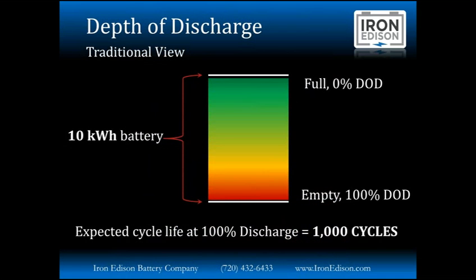Let's take a look, before we jump into the Schneider equipment, at something that's really important to know about comparing different types of lithium batteries. In a traditional view of depth of discharge versus cycle life, we've been trained over the years to look at a battery as full at 0% depth of discharge and empty at 100% depth of discharge. In this example, we're looking at a 10 kilowatt hour battery. And if we were to discharge this battery 100%, we would expect about 1,000 cycles of capacity until it reached what we call end of life. There's still some capacity remaining, but it's within the specifications where we say 1,000 cycles is going to be the maximum that this battery would provide, going from 0 to 100% depth of discharge.